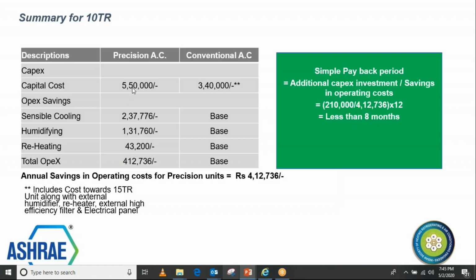So when you see here the capital cost for 1 unit, this is just one example, roughly about 5,50,000, and for the conventional it is 3,40,000. This 3,40,000 is not just the cost of the package unit. This is also the cost of the humidifier, the dehumidifier, and the reheaters which are required, and the control system, the control panel, the electrical panel, all these components to work together. In case of precision AC, the electrical panel, compressors, humidification, dehumidification, fans, coil, everything is built in as part of the system, so there is no additional cost to it.